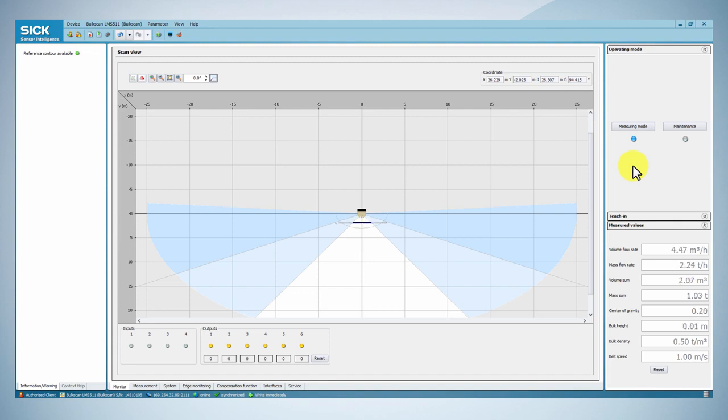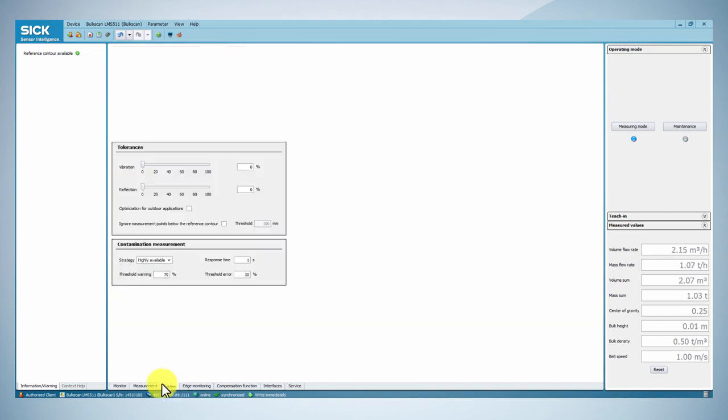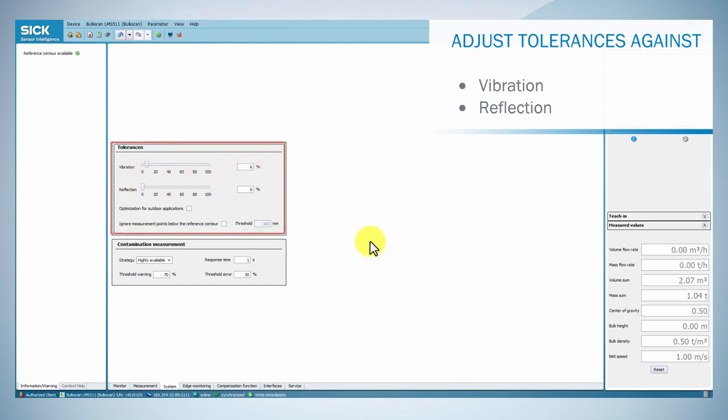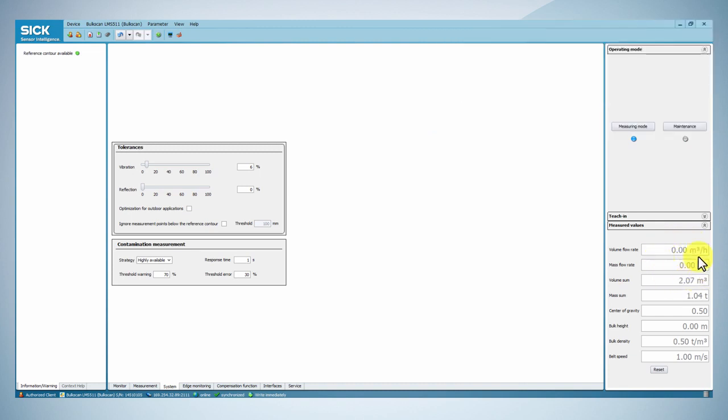In order to optimize measurement performance, you can set up the system parameters. Under the system tab, you can adjust the tolerances against vibration and reflection. Reduce or increase the tolerance against vibration so that the volume flow rate measured value remains constant at zero with an empty conveyor belt.